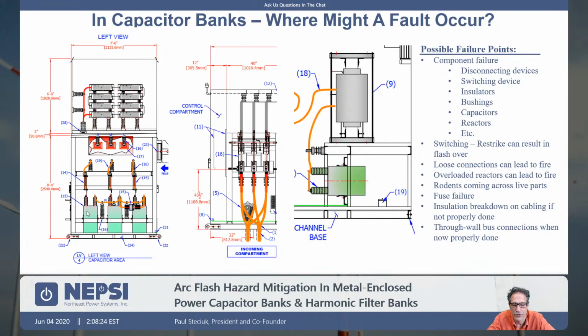That is unrelated to the manufacturer, NEPSI, in other words, the metal enclosed capacitor bank supplier, the failure within that capacitor. But we as a supplier have the ability to choose which capacitor to use and what voltage rating of the capacitor to use, and we can apply capacitors at a higher voltage rating, a higher impulse rating, and decrease their probability of failure. Capacitors themselves have a failure rate of just 1 in 5,000. So if you were to bump up the voltage rating of that capacitor and operate it at a lower voltage, in other words, a lower stress level, its reliability would go up even higher.